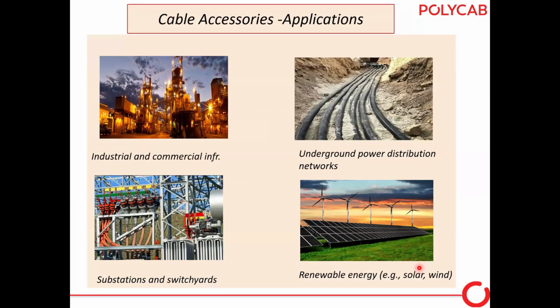Now, cable accessories applications. Wherever cables are there, heat shrink cable accessories are required. So: industrial or commercial infrastructure, underground power distribution networks, substation switchyards, and renewable energy. These are the different applications. As I said, where cable goes, accessories are required. We cannot use cables without accessories. Like at home, we can twist the wires, but in cables we cannot do that, for two reasons. One, you cannot twist, even if you use lugs and terminate, but XLPE cables are not for the open environment. That's why you have to do the termination for the cables.